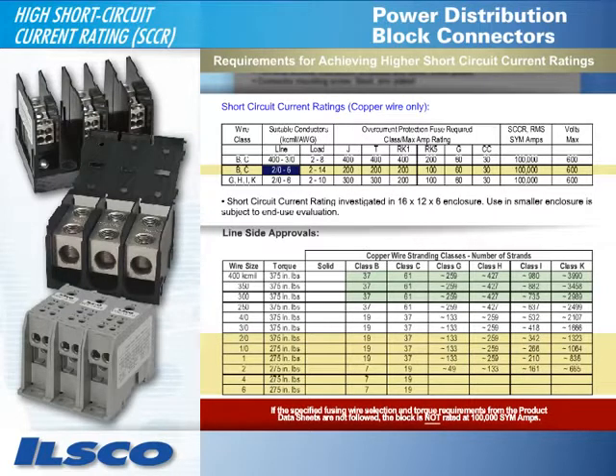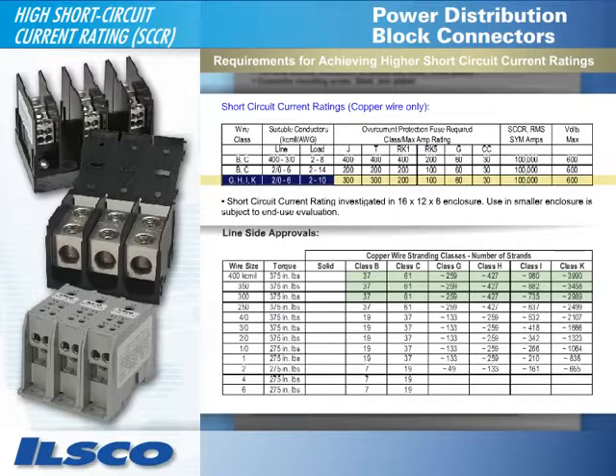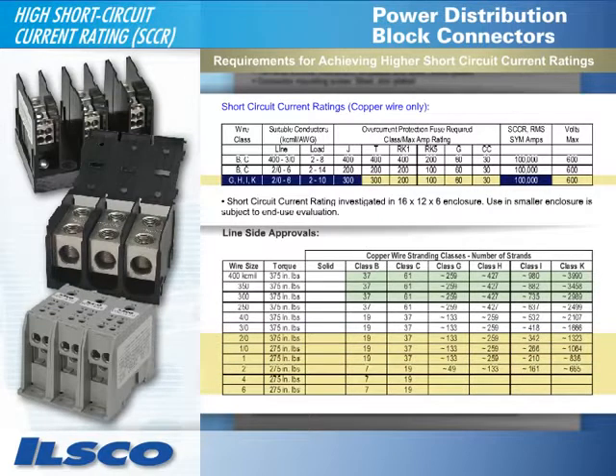One last example is from the high-flex wire indicated at the bottom of the chart. The wire conductor class is G, H, I, or K. Suitable conductors for line are 2-0 to 6; load is 2 to 10. For class J fuse ratings, it's 300 amps. This combination is also rated at 100,000 SYM amps. On the line-side approval chart, since the conductor range in this example is 2-0 to 6, the approved number of strands for each wire class is indicated in the highlighted cells. The necessary torque for this range of wire sizes is indicated here.